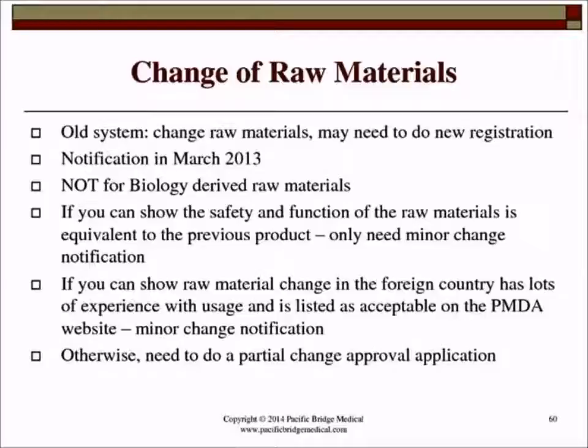So no review is performed by the PMDA, and your MAH just informs the MHLW of the change in raw materials. In the past, you would normally have to report this to the PMDA if the raw material supplier changed, but here you can just do a minor change notification instead of notifying the PMDA. Again, if the raw material change is in a foreign country that has an equivalent approval system, and it can be evaluated in terms of safety based on the history of adverse events or the absence of adverse events, and has lots of experience with the usage of the same raw material, and it's listed as acceptable on the PMDA website, a minor change notification can be done.